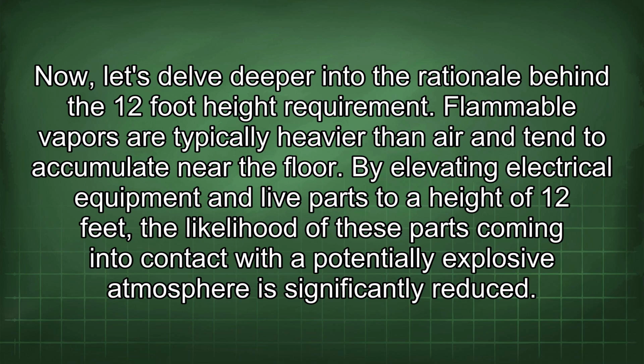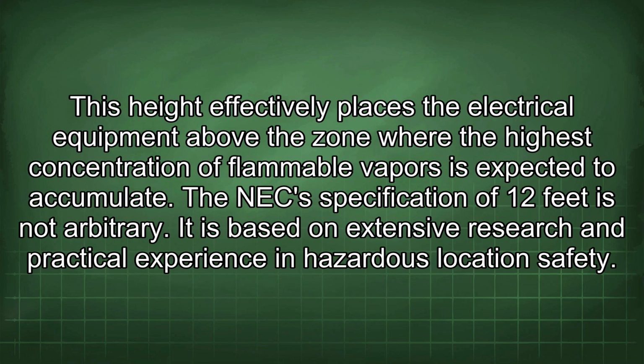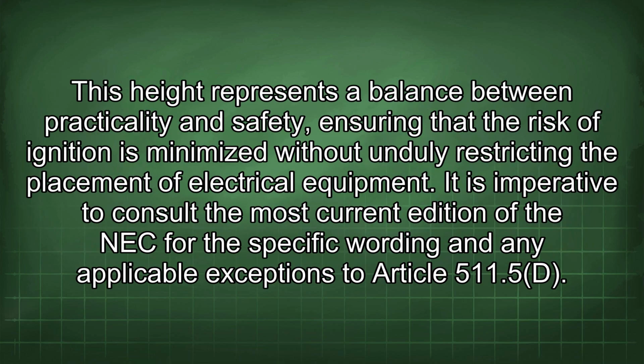Flammable vapors are typically heavier than air and tend to accumulate near the floor. By elevating electrical equipment and live parts to a height of 12 feet, the likelihood of these parts coming into contact with the potentially explosive atmosphere is significantly reduced. This height effectively places the electrical equipment above the zone where the highest concentration of flammable vapors is expected to accumulate. The NEC specification of 12 feet is not arbitrary. It is based on extensive research and practical experience in hazardous location safety. This height represents a balance between practicality and safety, ensuring that the risk of ignition is minimized without unduly restricting the placement of electrical equipment.